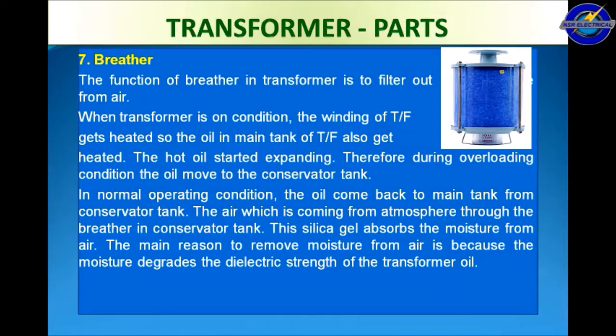When the transformer is on load, the winding of the transformer gets heated, so the oil in the main tank of the transformer also gets heated. The hot oil starts expanding. Therefore, during overloading conditions, the oil moves to the conservator tank. In normal operating conditions, the oil comes back to the main tank from the conservator tank.